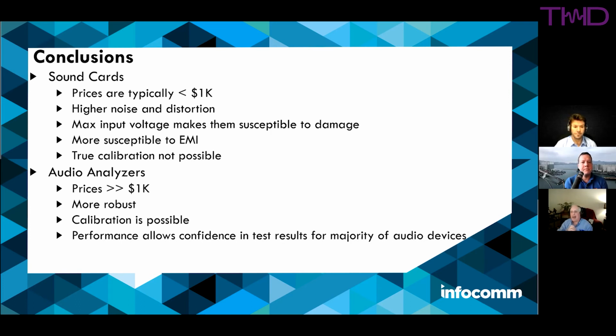However, you've got to be cognizant that they're typically going to be higher noise and distortion than an audio analyzer. If you are concerned that there might be, especially when measuring electronics, even if it's an amp or some device that doesn't have much gain, any concern that there might be some sort of voltage spike coming out of the device you're testing, sound cards can be much more susceptible to damage just because the front ends are not designed to handle tens of volts, let alone 100 volts plus going in there.